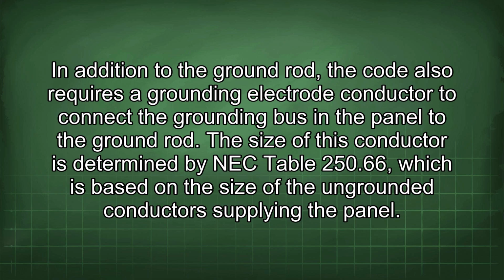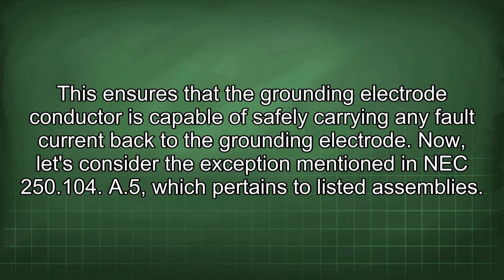In addition to the ground rod, the code also requires a grounding electrode conductor to connect the grounding bus in the panel to the ground rod. The size of this conductor is determined by NEC Table 250.66, which is based on the size of the ungrounded conductors supplying the panel. This ensures that the grounding electrode conductor is capable of safely carrying any fault current back to the grounding electrode.